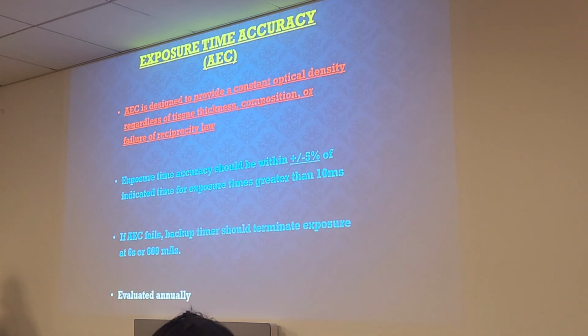So for your exposure time accuracy or your AEC, what does AEC stand for? AEC is designed for constant optical density regardless of tissue thickness. So if you set your AEC, let's say you're doing an abdominal x-ray, or a tib-fib, if you use the AEC, you still should get the optimal density, no matter the thickness of the body part. Your exposure time accuracy will be within plus or minus 5% for any exposure times that are greater than 10 milliseconds. And if your AEC fails, the exposure should terminate at either 6 seconds or 600 mAs max. So if you hear the exposure going for a really, really long time, that means your AEC is out of whack.